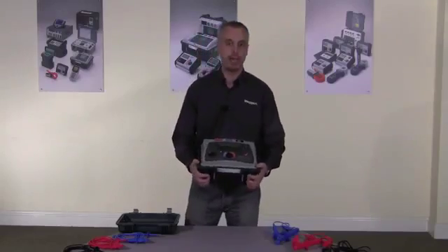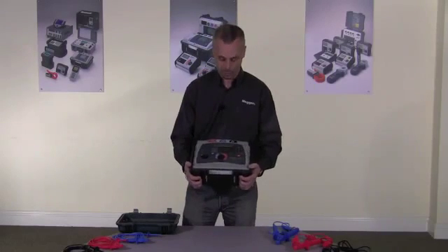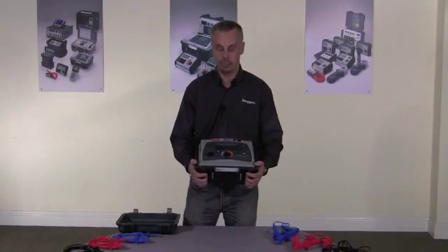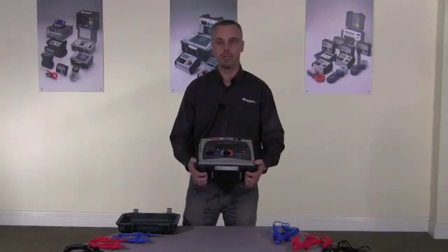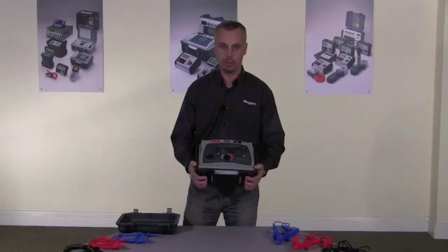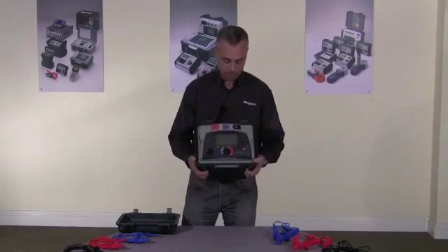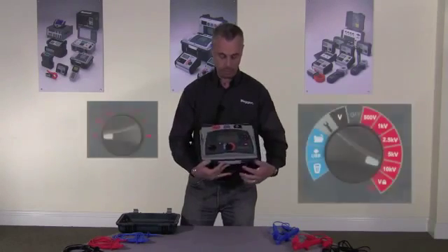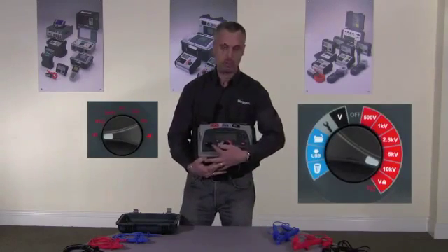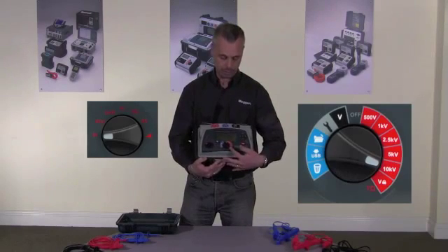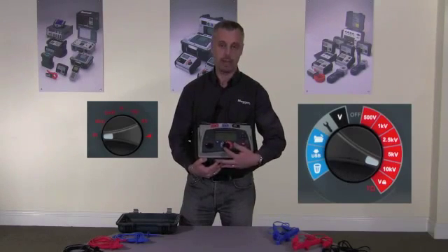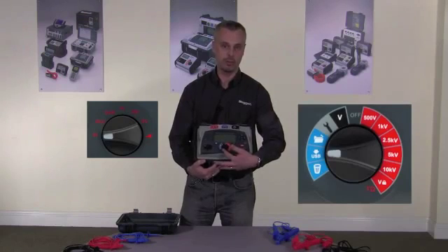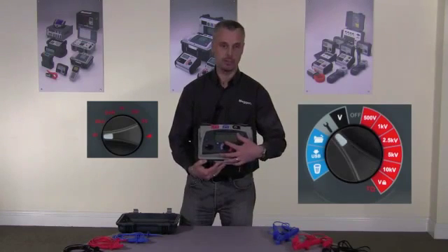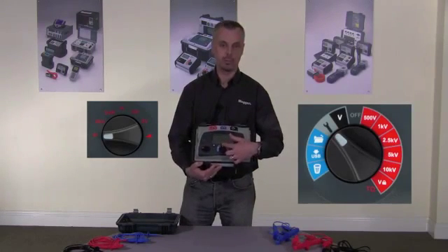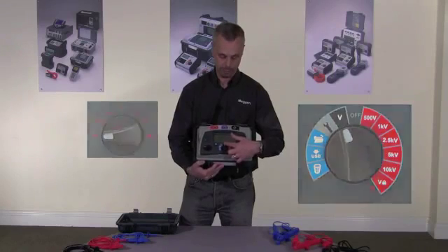With the feedback we had, and talking to the customers who use our instruments and any other instrument on the market, everybody has said how important it is for the instrument to be as easy and simple to use as possible. As you can see from the front panel, there are 2 rotary switches, one to select the mode and one to select the test voltage and other functionalities such as data storage and download and the settings. There's also the addition of a separate voltage measurement range.